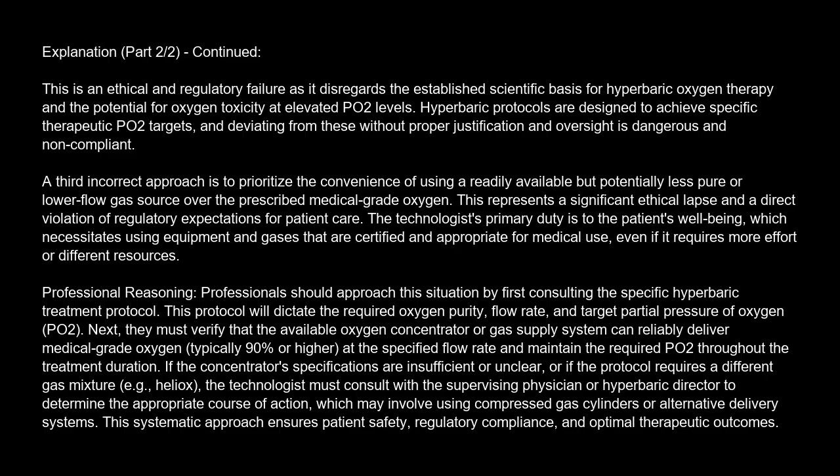This protocol will dictate the required oxygen purity, flow rate, and target partial pressure of oxygen, PO2. Next, they must verify that the available oxygen concentrator or gas supply system can reliably deliver medical-grade oxygen, typically 90% or higher, at the specified flow rate and maintain the required PO2 throughout the treatment duration.